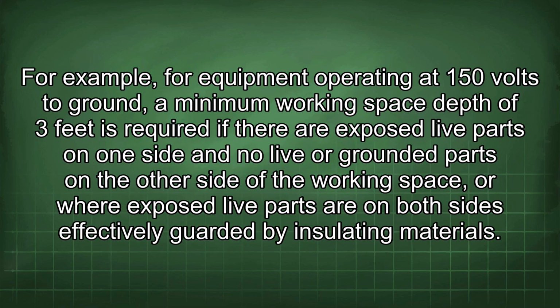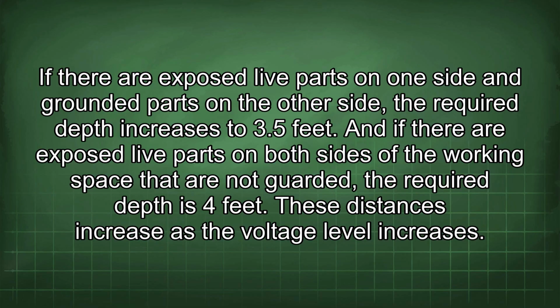For example, for equipment operating at 150 volts to ground, a minimum working space depth of 3 feet is required if there are exposed live parts on one side and no live or grounded parts on the other side of the working space, or where exposed live parts are on both sides effectively guarded by insulating materials. If there are exposed live parts on one side and grounded parts on the other side, the required depth increases to 3.5 feet. And if there are exposed live parts on both sides of the working space that are not guarded, the required depth is 4 feet. These distances increase as the voltage level increases.